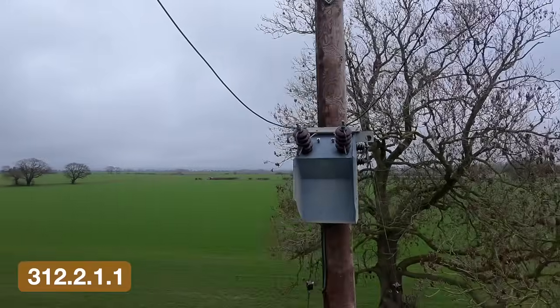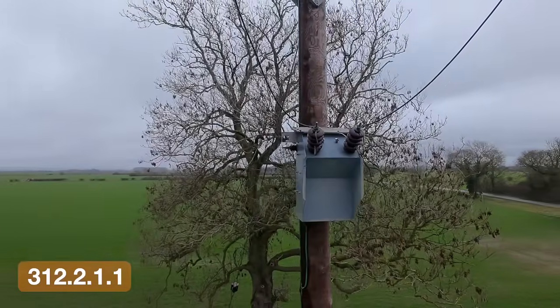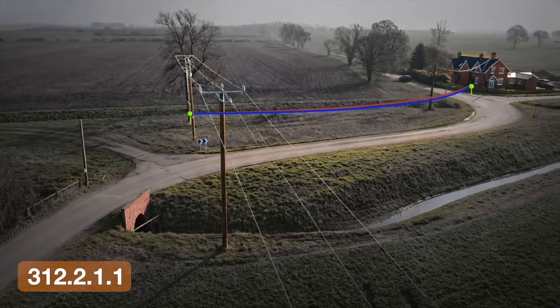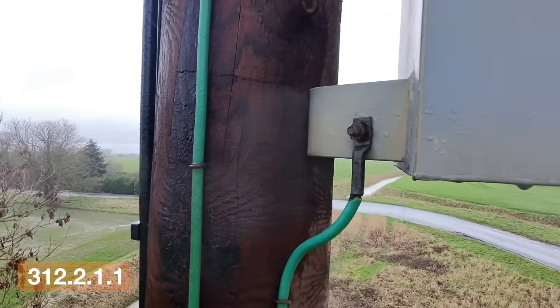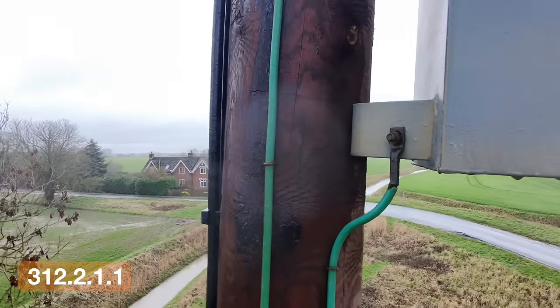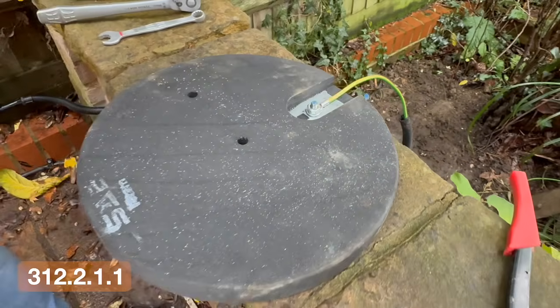PNB earthing is now formally recognised within BS 7671. PNB stands for Protective Neutral Bonding. It is not a new earthing system that you will go out and install. It is a type of supply arrangement provided by the network. In simple terms, the neutral conductor is connected to earth at a point between the transformer and the consumer's supply terminals. So instead of being earthed only at the transformer, it is earthed again closer to the installation.